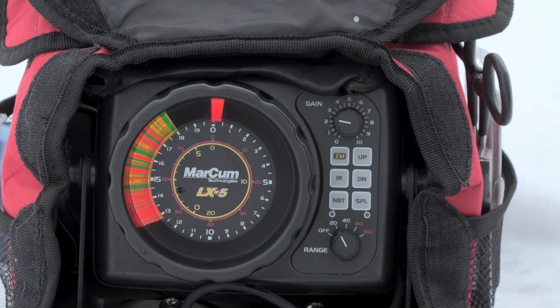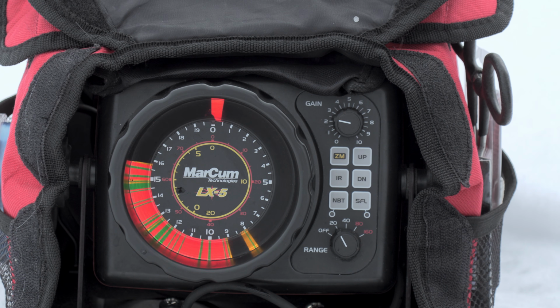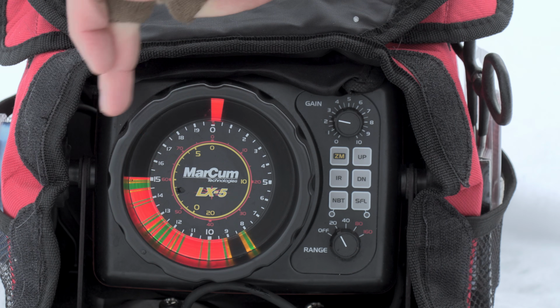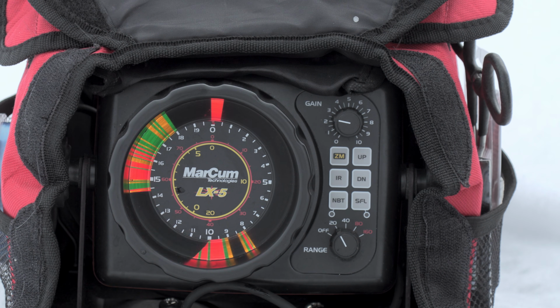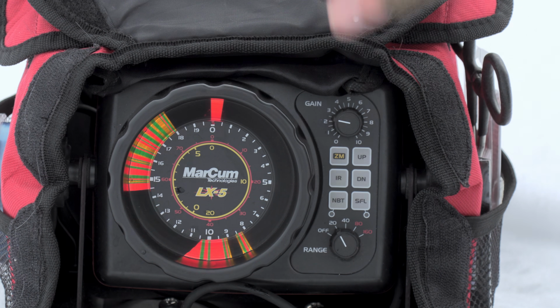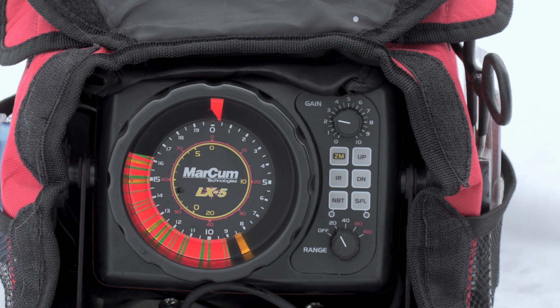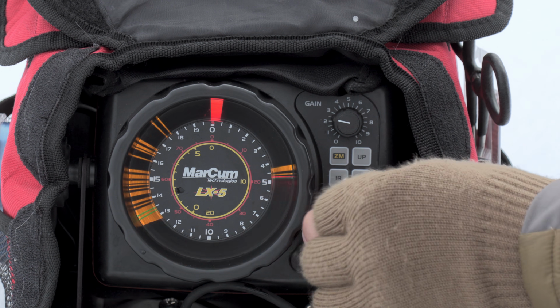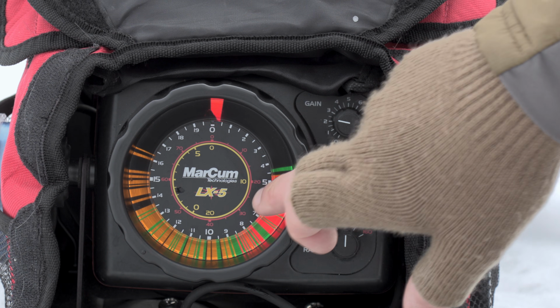Starting at the 12 o'clock position, that's wherever your transducer is at. Your 6 o'clock position is 10 feet. If you see 9, it's 15. Coming all the way back up near the 11 o'clock position, you see 19. Say if it was 30 feet, it would just look blank, and you'd have to turn it over to 40. So the bottom, see, it's about at 4.5, so I'd have to double that, which would put it at 9.